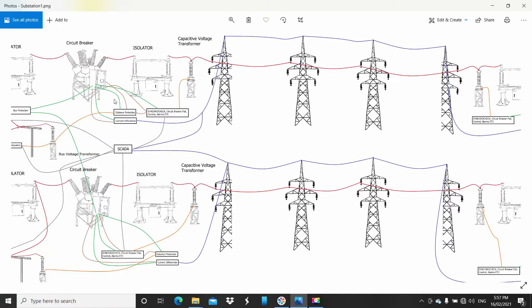If there was a fault, that would short circuit or bypass the load on the system, creating a very high current, leaving only the impedance of the line left in the circuit. The impedance relay would kick in. We know what the impedance of the line is. Say if the line is 10 ohms, then we could program in the line impedance into the relay, so then it would know when anything is less than 10 ohms, for example.